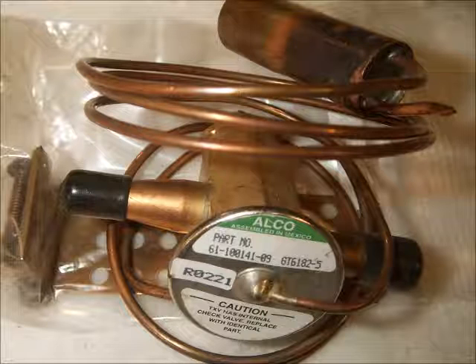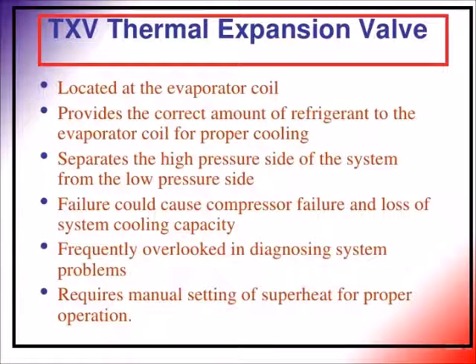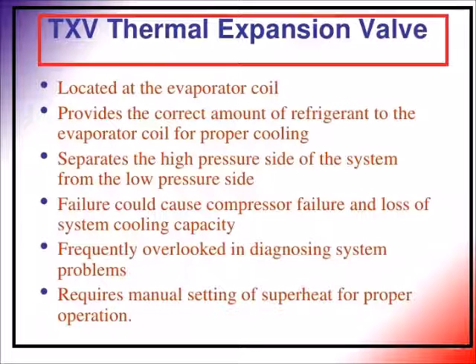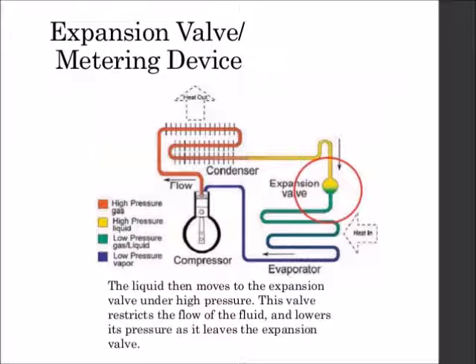As a refrigerant passes through a circuit containing these 4 elements, air conditioning occurs. The cycle starts when refrigerant enters the compressor in a low-pressure, moderate-temperature, gaseous form. The refrigerant is compressed to a high-pressure and high-temperature gaseous state. The high-pressure and high-temperature gas then enters the condenser, which converts it to a high-pressure liquid by transferring heat to a lower-temperature medium, usually ambient air. The high-pressure liquid then enters the expansion valve where the TX valve allows a portion of the refrigerant to enter the evaporator.